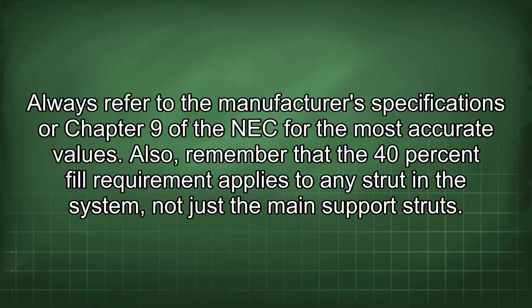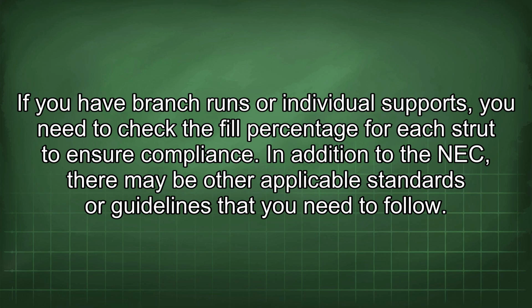Also, remember that the 40% fill requirement applies to any strut in the system, not just the main support struts. If you have branch runs or individual supports, you need to check the fill percentage for each strut to ensure compliance. In addition to the NEC, there may be other applicable standards or guidelines that you need to follow.